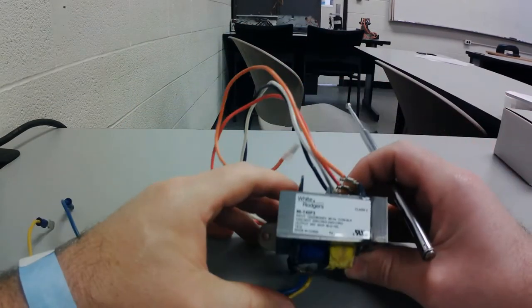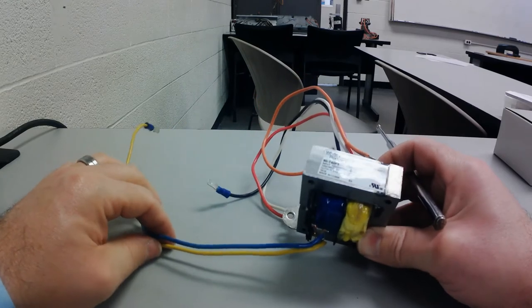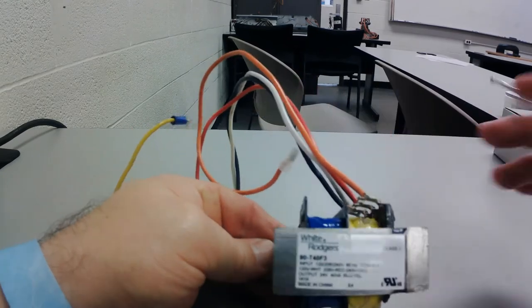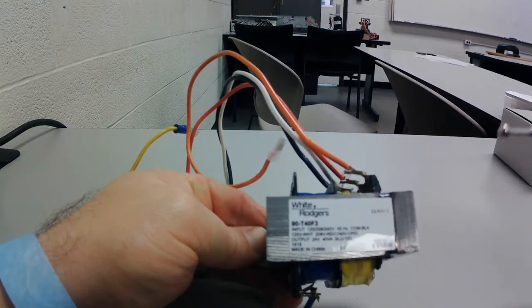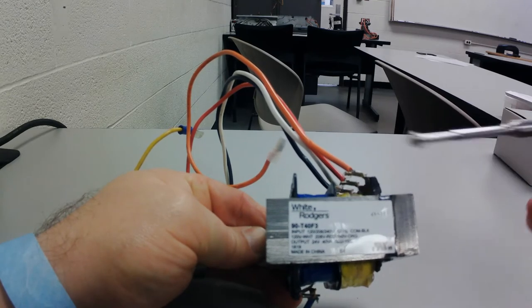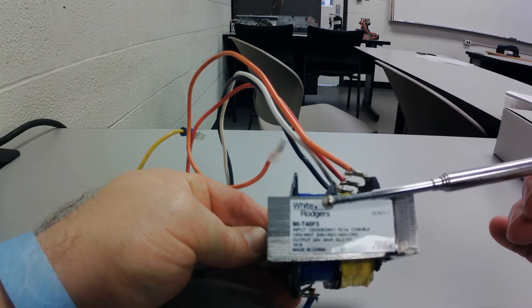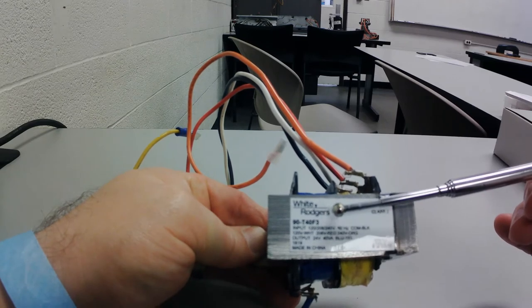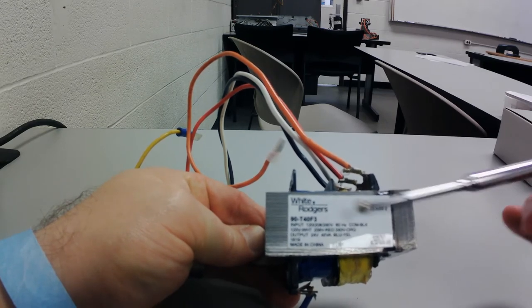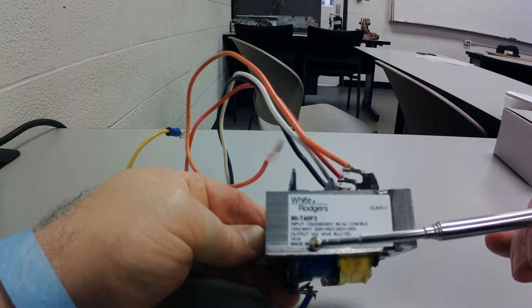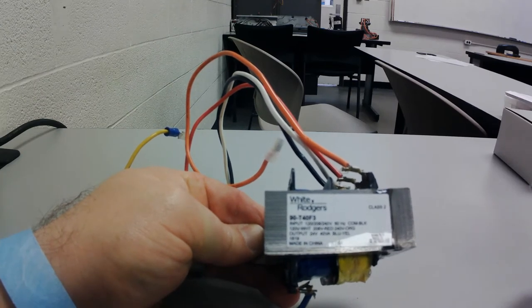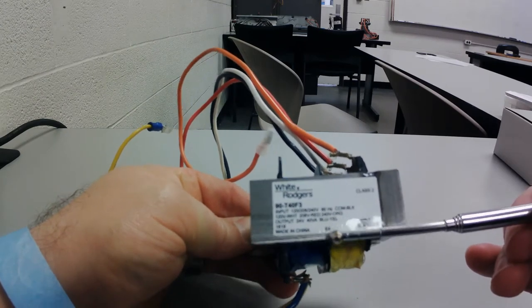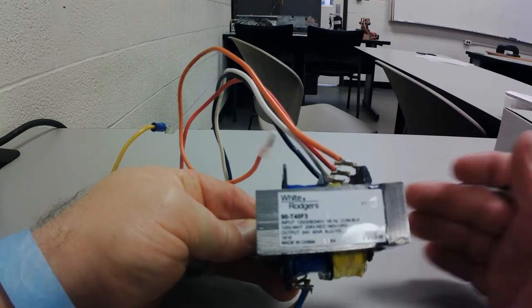Likewise, this is a White Rodgers multi-voltage transformer. If we look at the front, you can see that it's got your model number, it's got your manufacturer name, White Rodgers, and the input can be 120, 208, or 240. The output is always going to be 24 volts with a 40 volt amp rating. And it lists here that the blue and yellow wires are my 24 volt side.